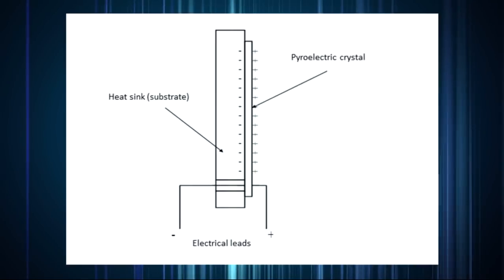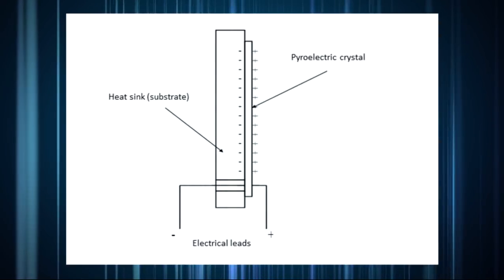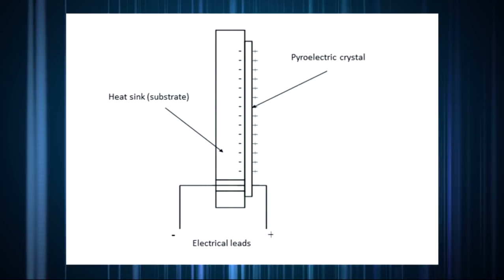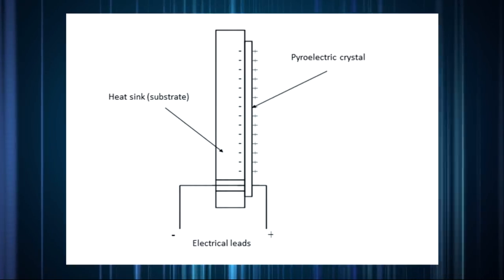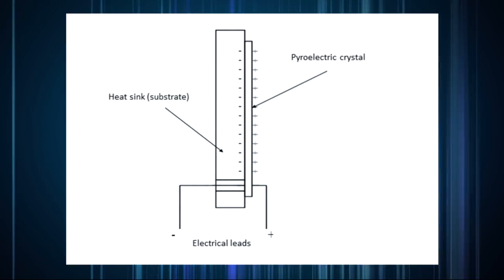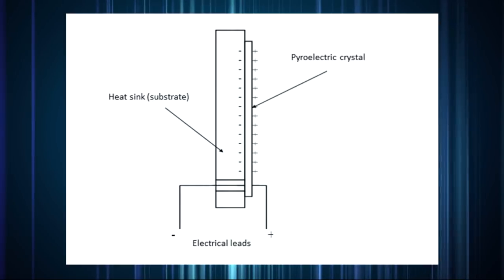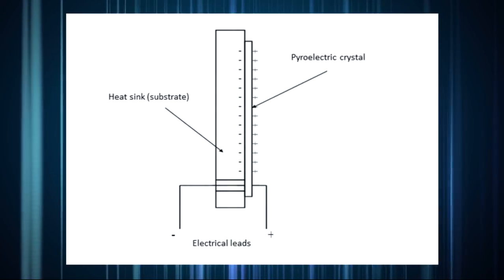This means the charge is proportional to the energy that was in the laser pulse. The two surfaces of the crystal are metal coated, so the coated crystal in effect becomes a capacitor. The total charge generated is collected and becomes a voltage pulse, which then gets measured.